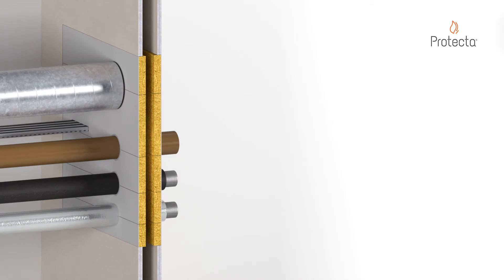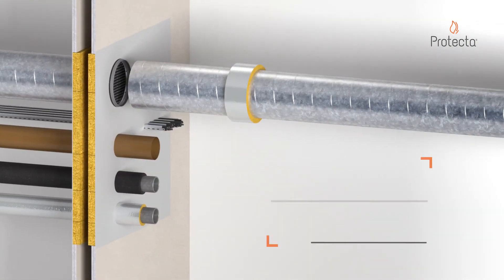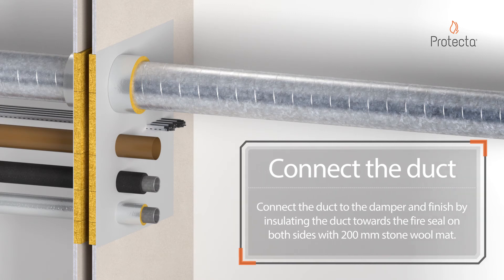Repeat the process on the other side of the wall. Connect the duct to the damper and finish by insulating the duct towards the fire seal on both sides with 200mm stone wool mat.